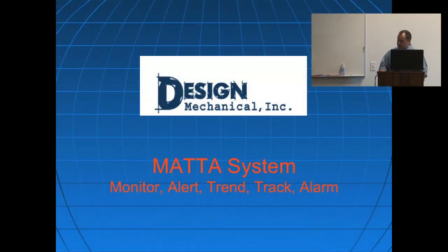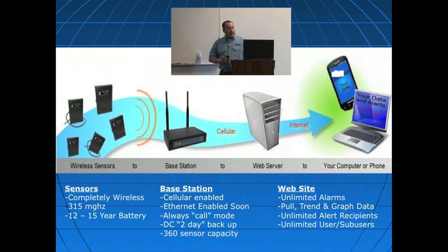The MATTA system is very versatile. In a nutshell, it's a stand-alone wireless system where you deploy a series of small battery-powered sensors about the size of a deck of cards. They're entirely battery-powered off of common double-A batteries — in this case, lithium-ion for the longest shelf life. Most sensors enjoy a 10-year-plus battery life. A water sensor can last more than 12 years, and a temperature sensor giving 20-minute readings can last more than 10 years. If you add up the time and expense of changing batteries, having them last that long is a good benefit.